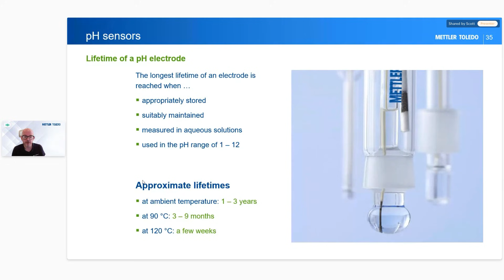So the first thing is storing our pH electrode. When we're storing our pH electrode, what we're trying to do is ensure that the gel layer we had on the bottom of the electrode, on the bulb, remains hydrated and ion rich. So what we can do is store it in special storage solution. You can find some from Mettler Toledo and other brands as well that have special storage solutions. If you don't have special storage solution, the next one is the electrolyte solution that's inside. So the inside here was the electrolyte, and we should store it in that electrolyte. Generally, that is 3 molar potassium chloride.